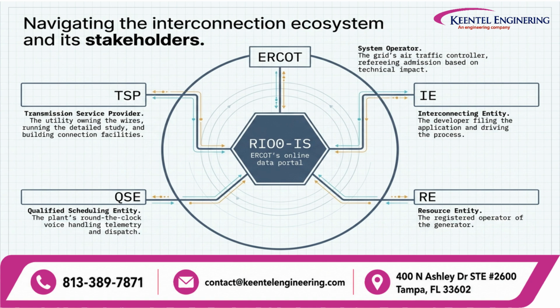Transformer protection doesn't exist in isolation. Especially for generation and transmission projects, protection engineering operates within a larger interconnection ecosystem. At the center of this ecosystem is the system operator. In this example, ERCOT acts as the system operator, effectively serving as the grid's air traffic controller and evaluating interconnection based on technical impact. The transmission service provider, or TSP, owns and operates the transmission infrastructure.